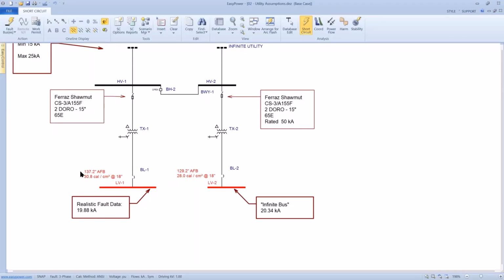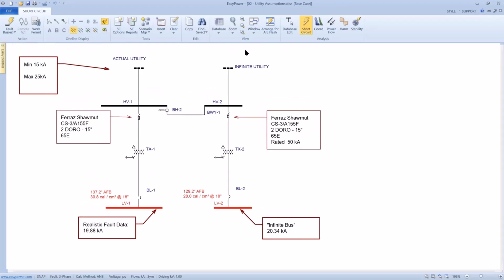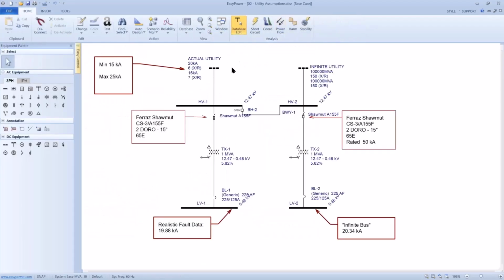So if we're going to stay on the safer side, we want to be a little bit more conservative in selecting the value for our realistic source. Now, how do you do that? Well, first of all, I'm going to go back to database edit, and I'm going to build two scenarios. The scenario manager, I've built two values. Let's just reopen one line. I built a value with maximum utility, so I take the 20,000 and bump it up by 25% to get 25. And the minimum, I take away 5,000 amps.